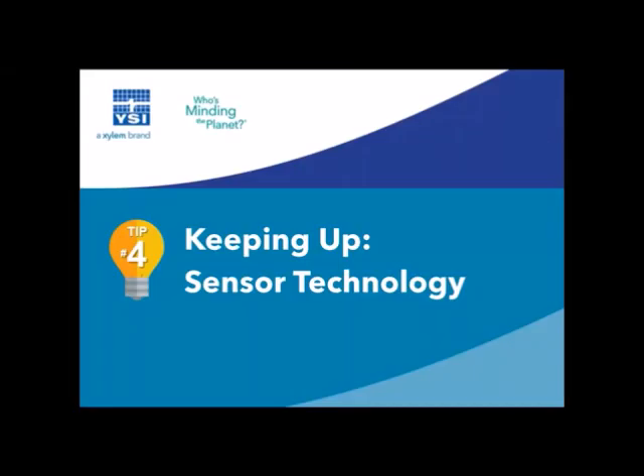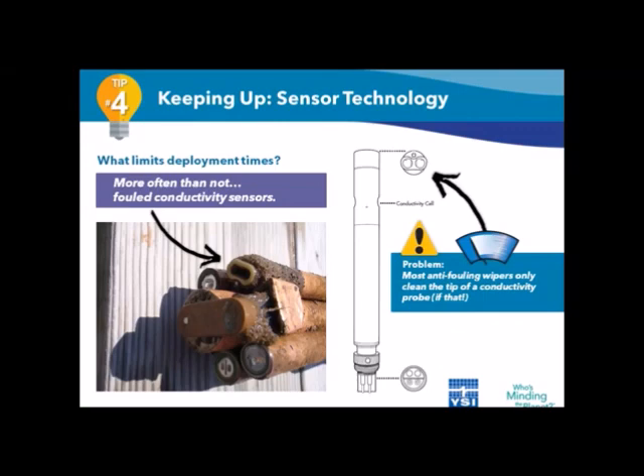All right, thanks, Tiffany. So tip number 4 is always to keep up to date with new sensor technology. Even though a lot of the anti-fouling tips we've described so far are great, there's one Achilles heel to most anti-fouling solutions, and most of us know this as the conductivity probe or conductivity sensor. Most conductivity cells are going to be susceptible to interference from fouling in one way or another.